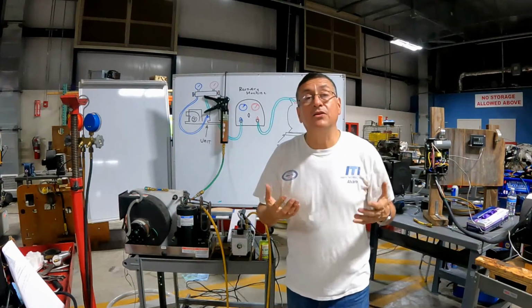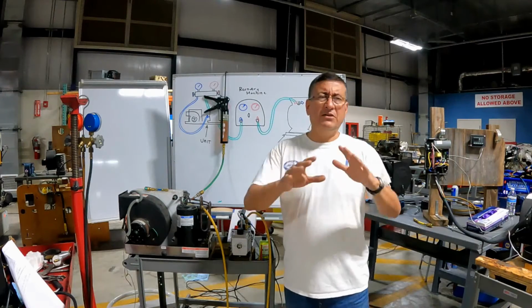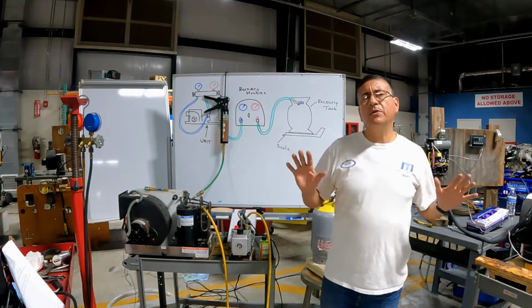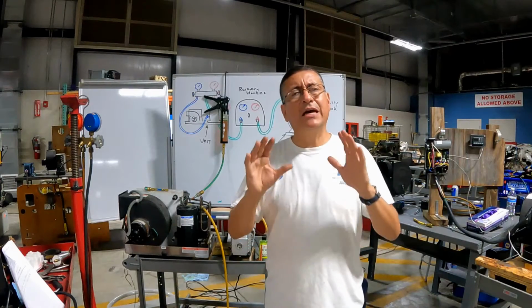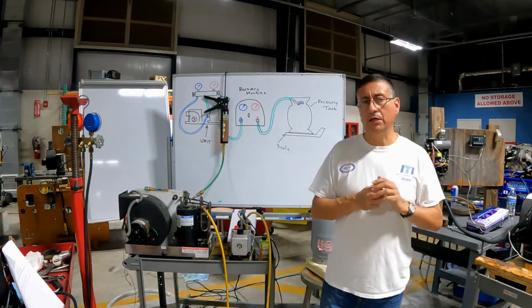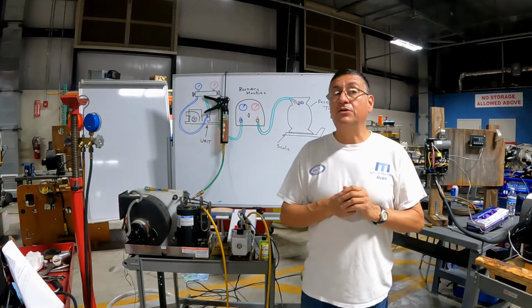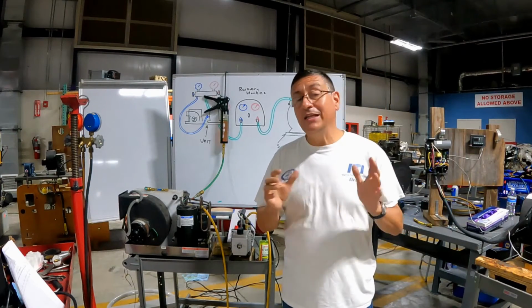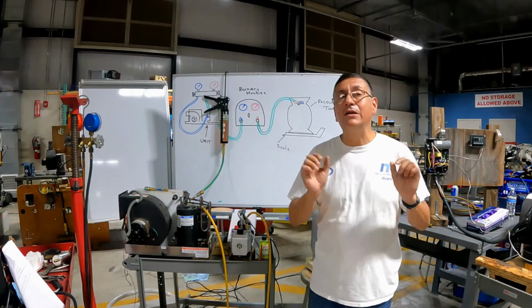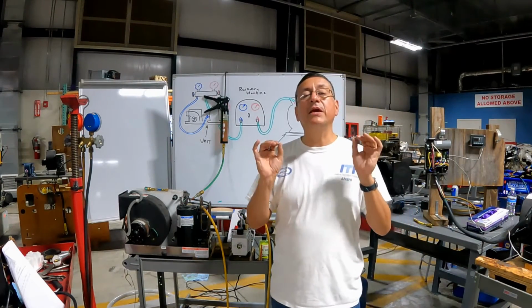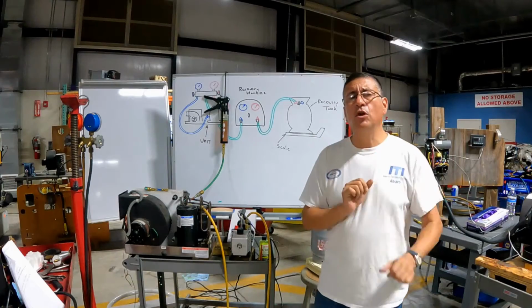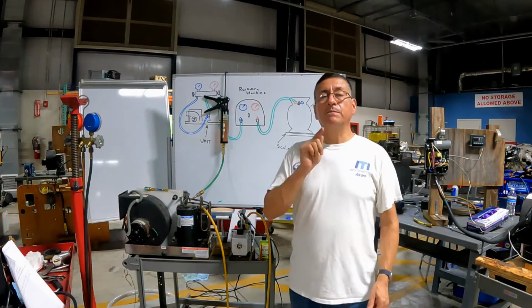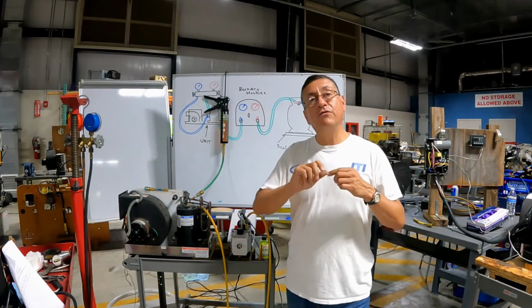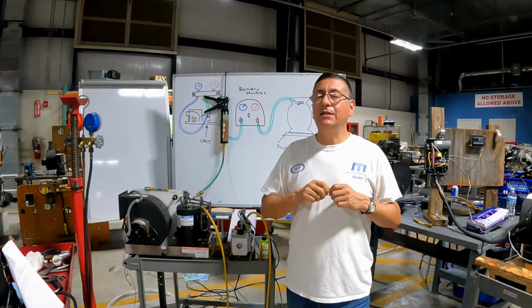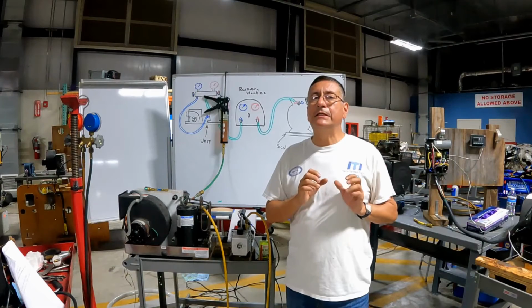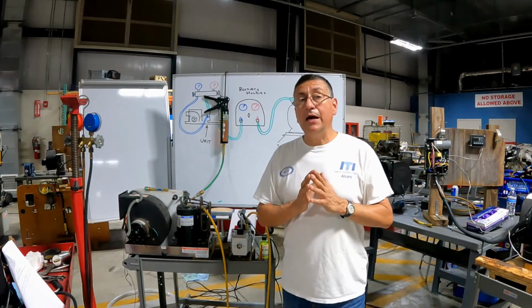How can you verify that you don't have leaks? No, my system is hermetic. I am 100% sure that I don't have leaks because this system is hermetic. Are you sure? Because all systems have little micro leaks. A fully hermetic system is impossible. All systems have small leaks, especially in marine application, because there we use a lot of fittings, flare fittings, and those fittings have leaks. It's not 100% tight.